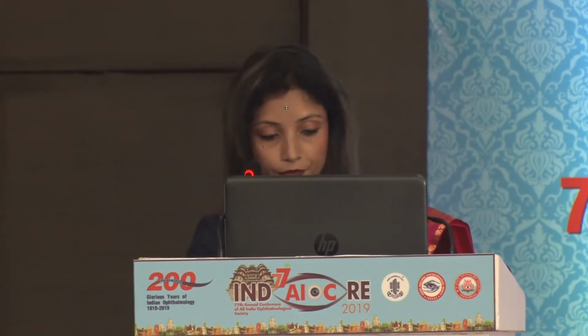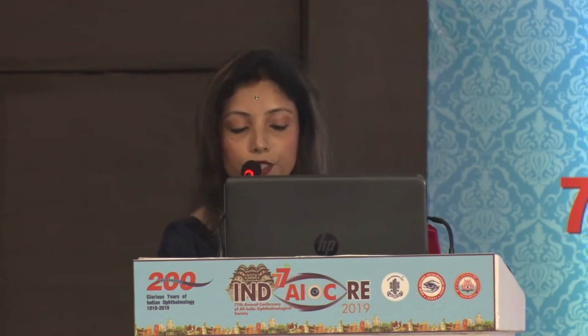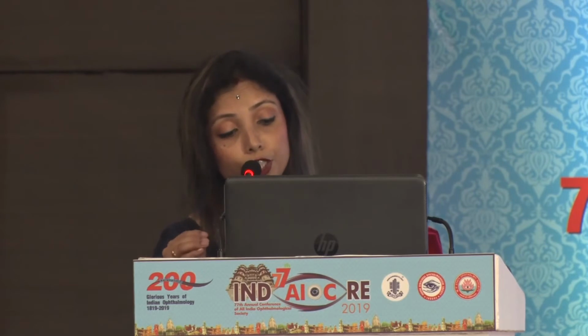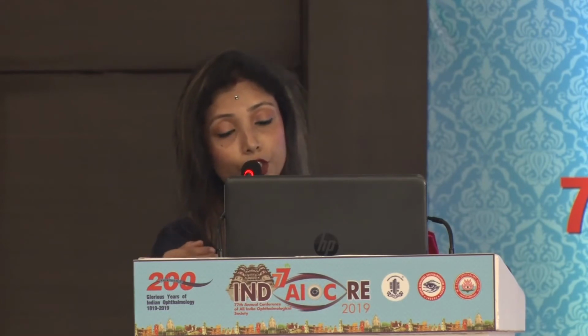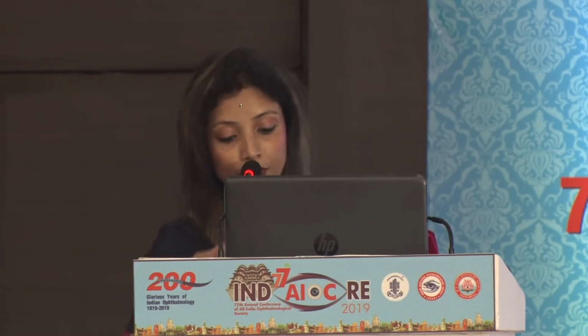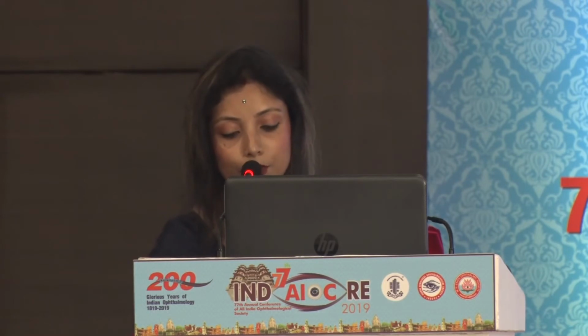We have a lot of hollow instruments in our vitrectomy and phaco machines. All the hollow instruments, the irrigation aspiration cannula as well as the phaco handpiece, need to be flushed with distilled water 3 times. That flushing, as you can see here, is being done with a 60 cc syringe and not a 10 cc syringe. Thrice we flush with distilled water, we throw that distilled water, and thrice the flushing will be done by air. So that makes 6 times flushing.